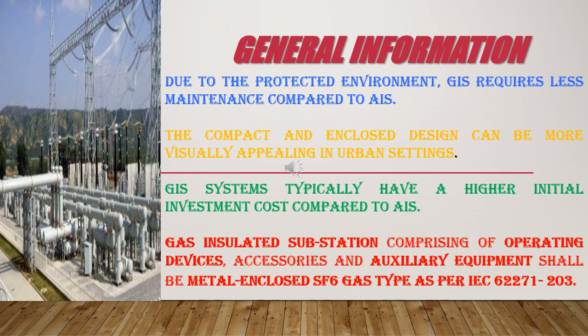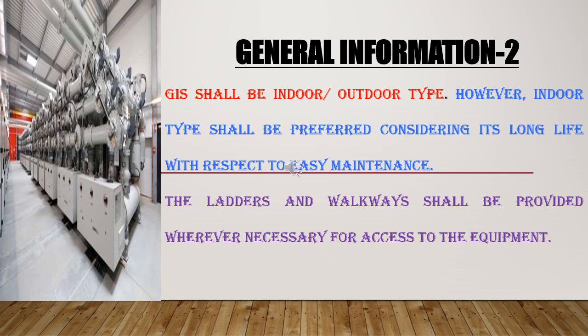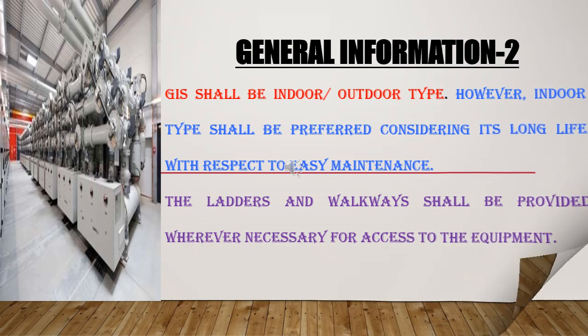Gas Insulated Sub-station comprising of operating devices, accessories and auxiliary equipment shall be metal-enclosed SF6 gas type as per IEC 62271-203. GIS shall be indoor-outdoor type. However, indoor type shall be preferred considering its long life with respect to easy maintenance. The ladders and walkways shall be provided wherever necessary for access to the equipment.